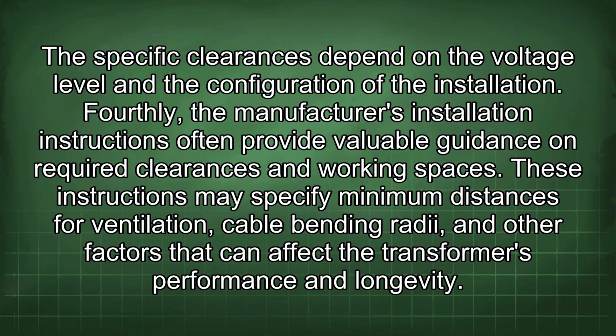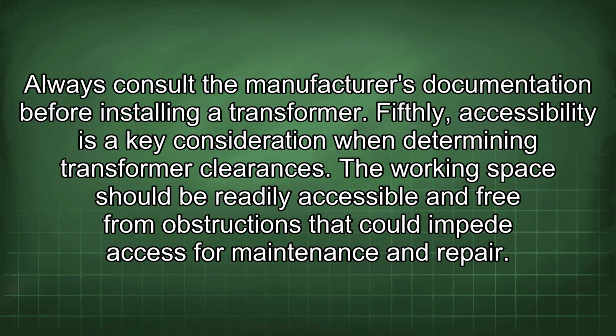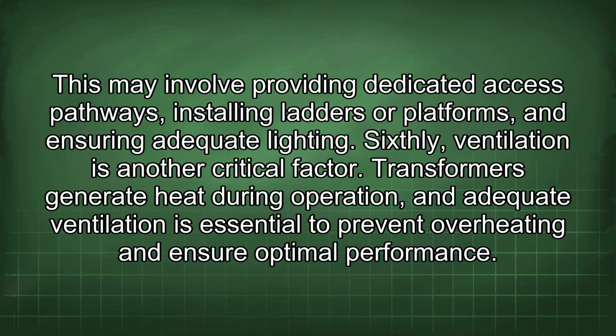These instructions may specify minimum distances for ventilation, cable bending radii, and other factors that can affect the transformer's performance and longevity. Always consult the manufacturer's documentation before installing a transformer. Fifthly, accessibility is a key consideration when determining transformer clearances. The working space should be readily accessible and free from obstructions that could impede access for maintenance and repair. This may involve providing dedicated access pathways, installing ladders or platforms, and ensuring adequate lighting.